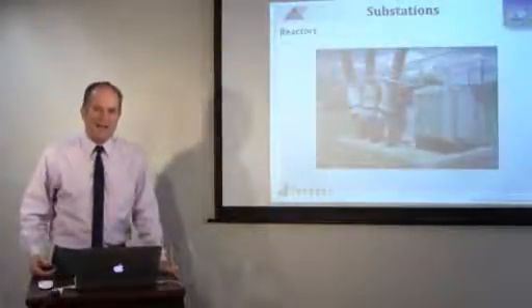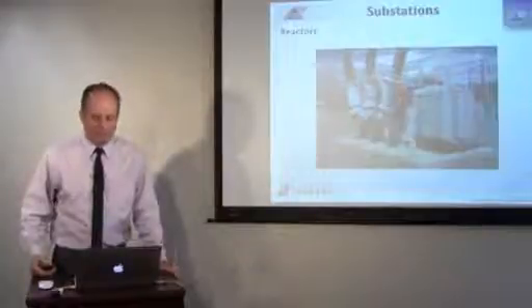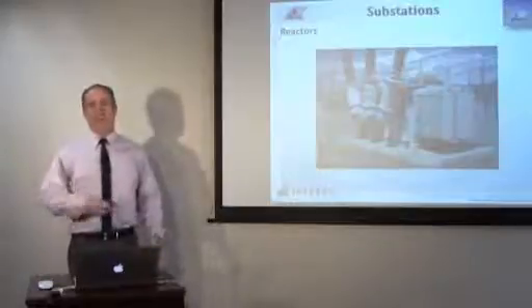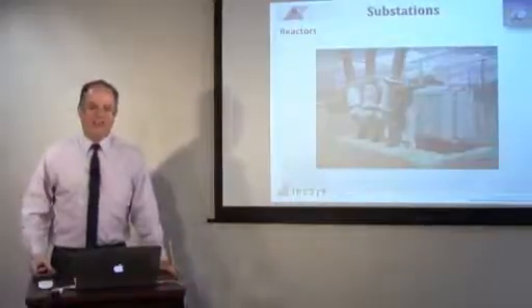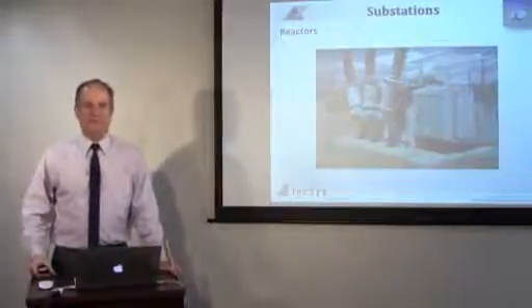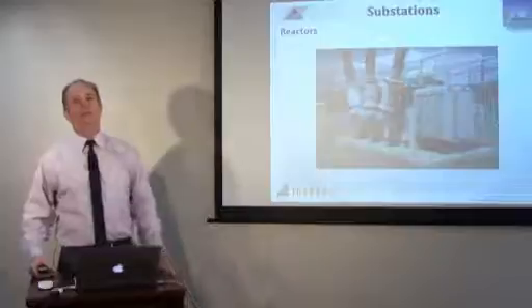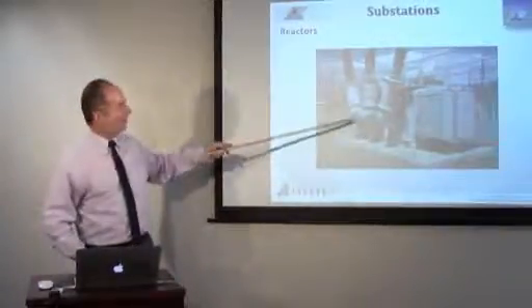Opposite are reactors. Now, reactors are the term used for inductors. So you have capacitors and inductors, but in power systems they don't call them inductors, they call them reactors. I don't know why, maybe because of reactants or something, but they're called reactors. This is a 345 kV reactor. All it is is a coil of wire to ground, three of them, one for each phase. A transformer would have two sets of coils, so you can transform voltage up and down. This is just a reactor. It's just a coil to ground.